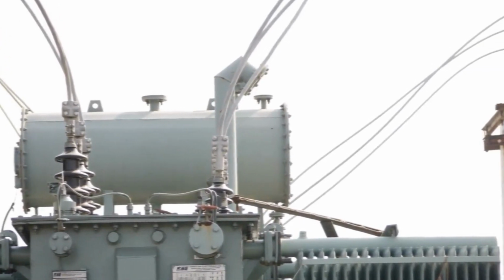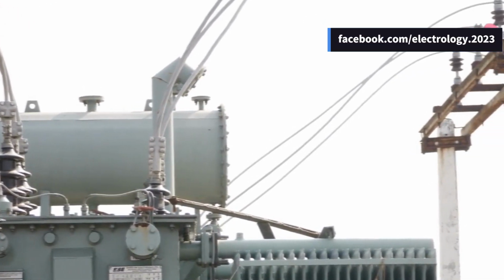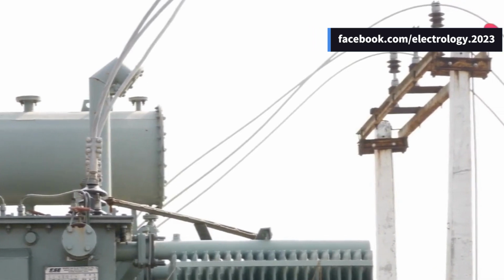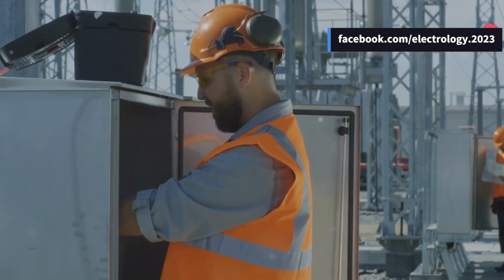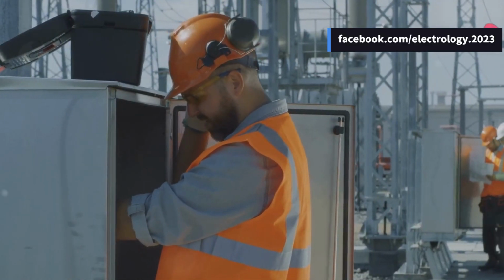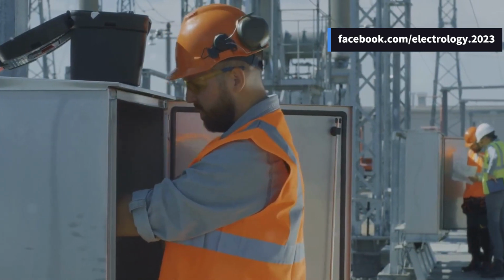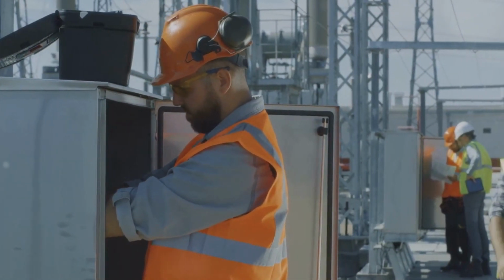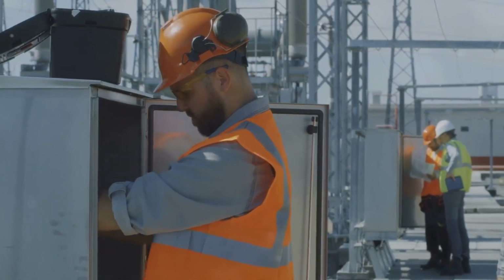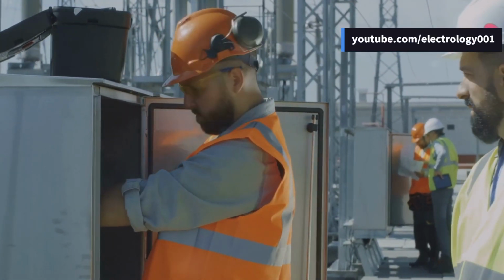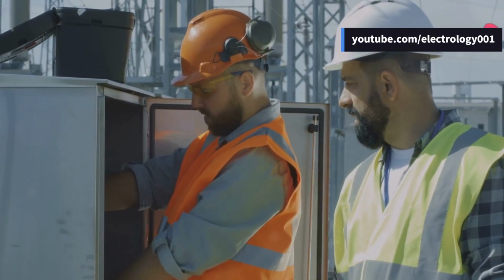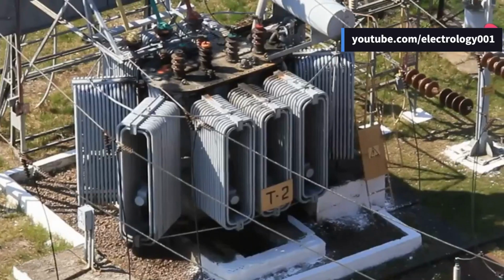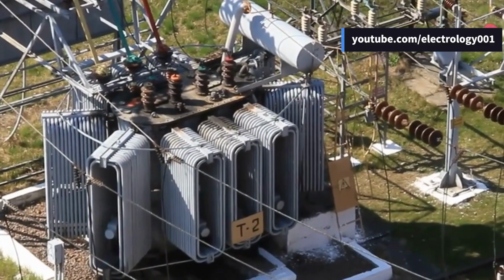Now you might be wondering, why is it more economical to install numbers of smaller rated transformers in parallel than installing a bigger rated electrical power transformers? Well, this has mainly the following advantages. Efficiency. Transformers are most efficient at full load. By using parallel transformers, you can only run what's needed, keeping them closer to full load for better efficiency.